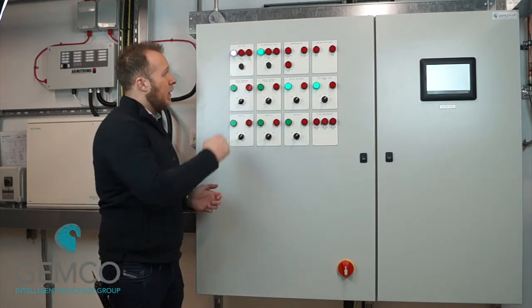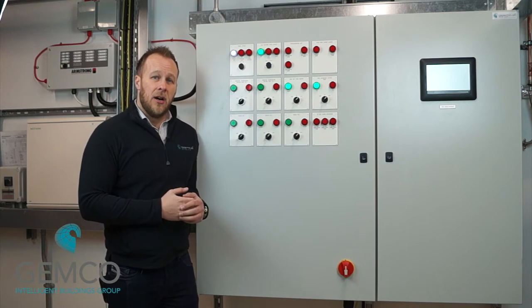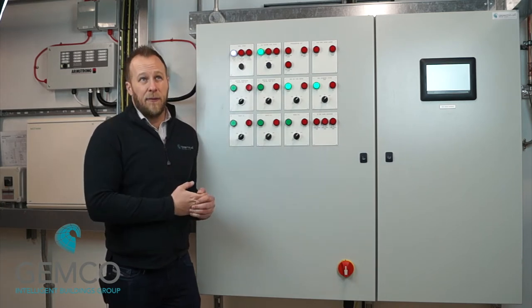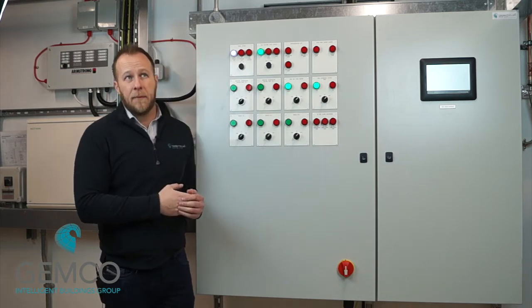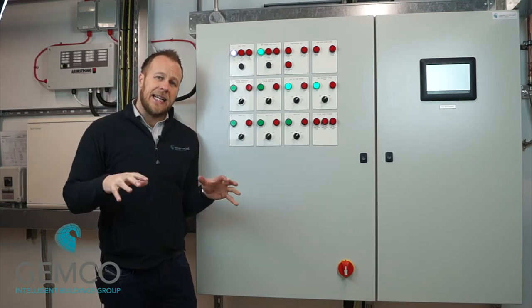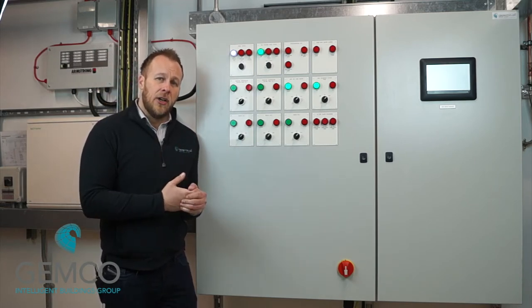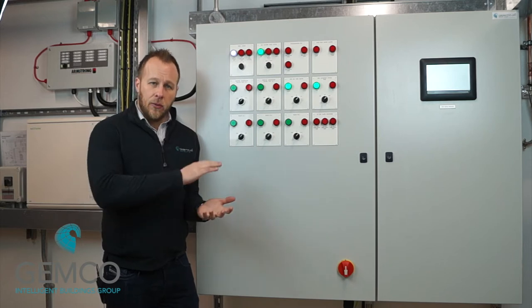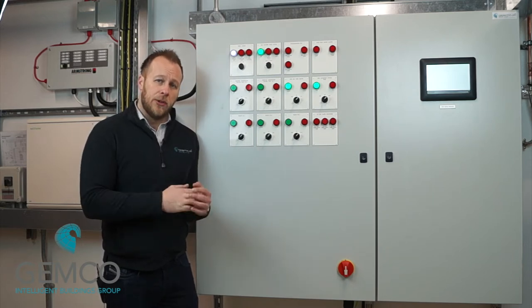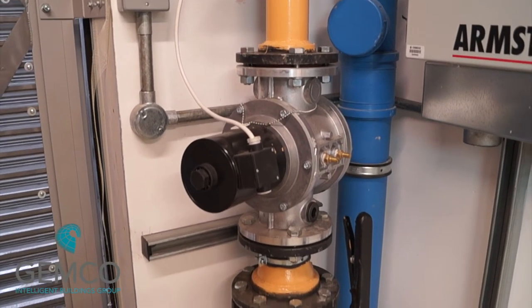The second lamp on the label is the gas detection alarm. So there's a gas sniffer above the boilers up there, little black box, and that detects the gas in the air. And if the gas goes above the preset level, that will shut off the plant. That will shut down your gas solenoid, which I'll come on to in a minute.